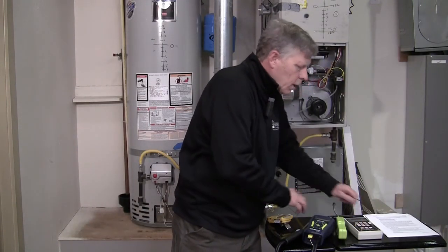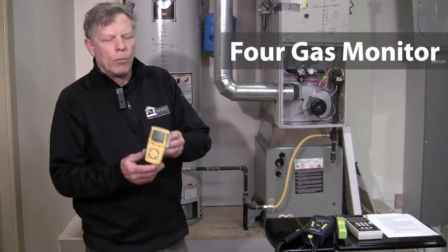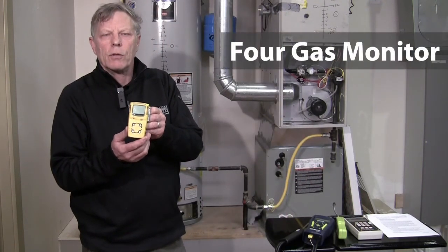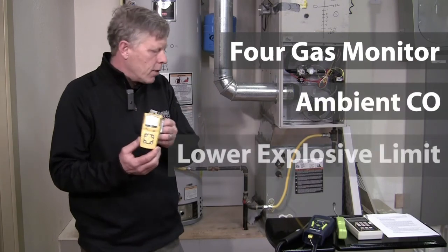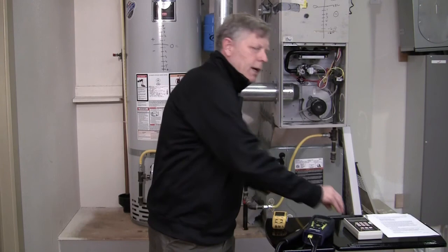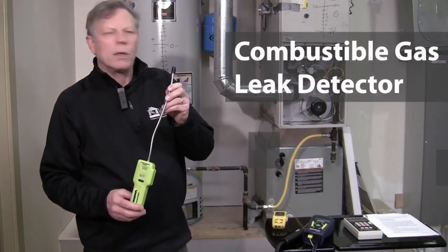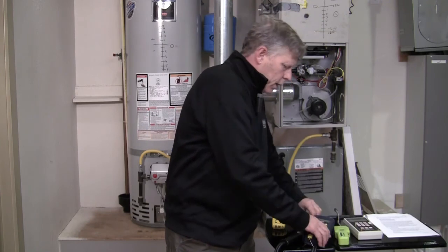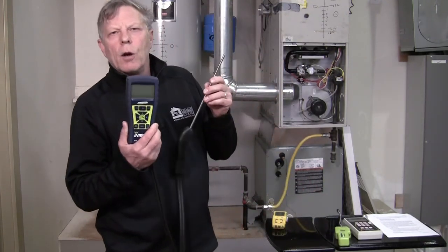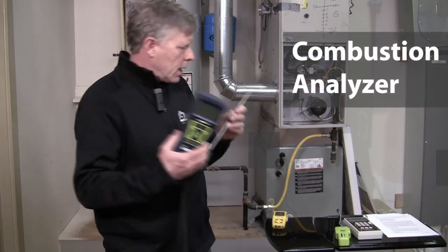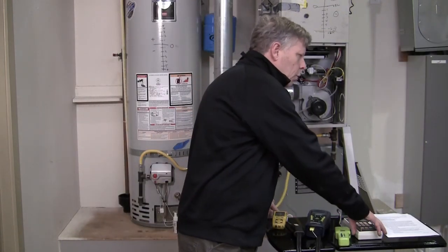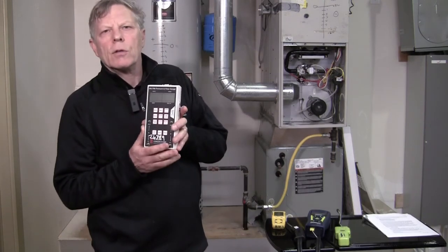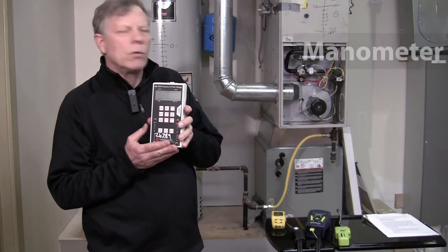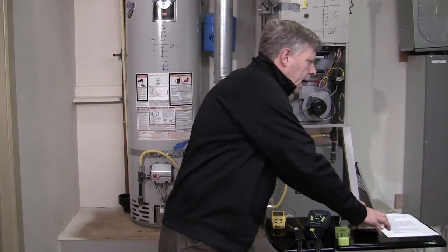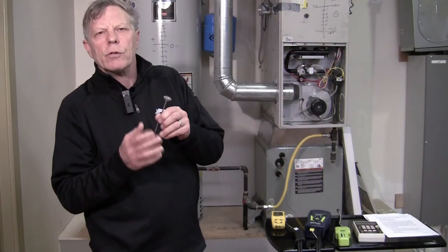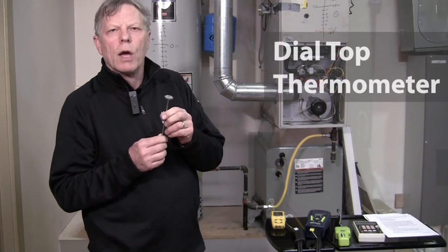Also, we're going to use a few tools to do the test. We're going to use a 4-gas monitor that's going to monitor ambient CO and the LEL for us while we're testing. We're going to test our gas piping with a combustible gas leak detector. We're going to test our carbon monoxide in our appliances with our combustion analyzer. We will need to set up for some spillage testing, so we will need to measure the pressure in the combustion appliance zone with a manometer, and we'll be measuring heat rise in forced air furnaces, so we'll be using a dial top thermometer for that.